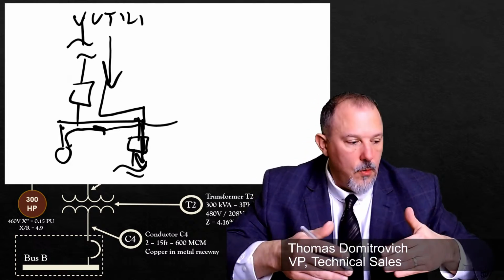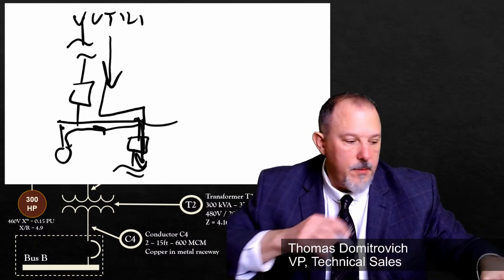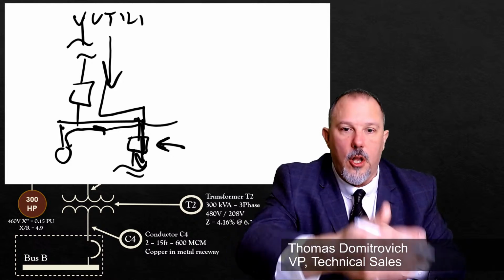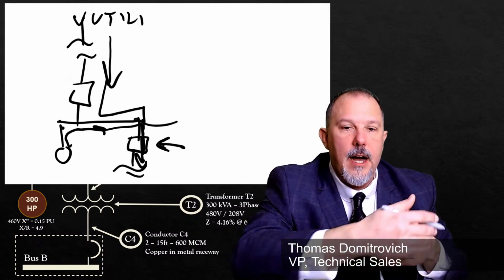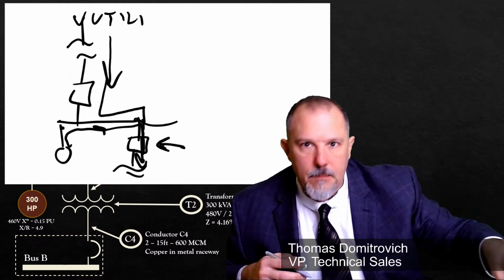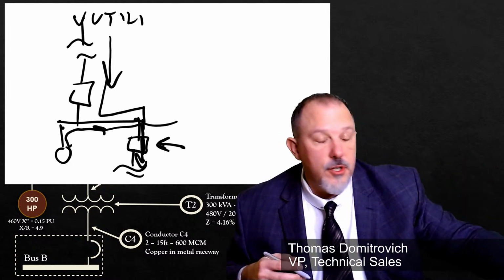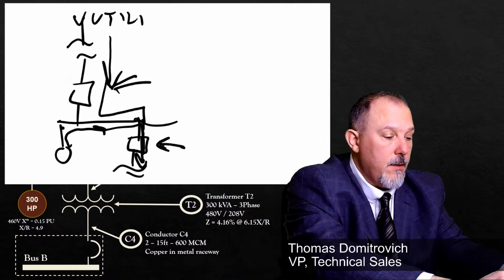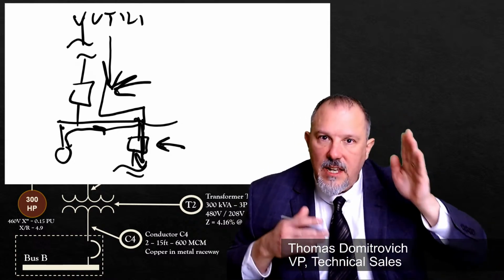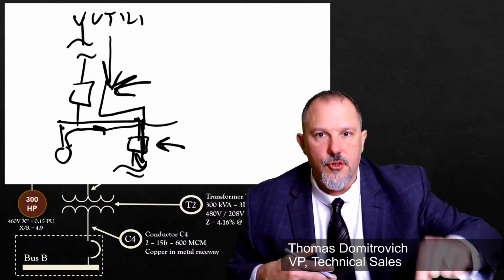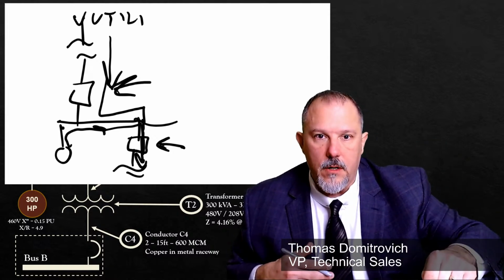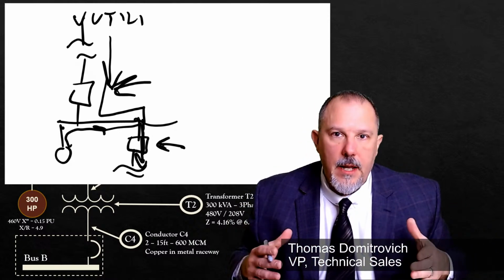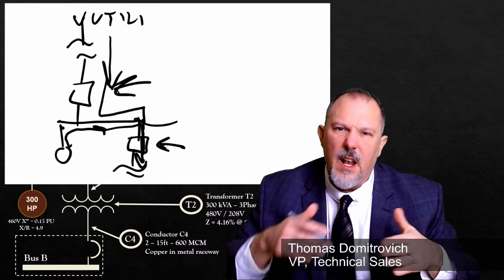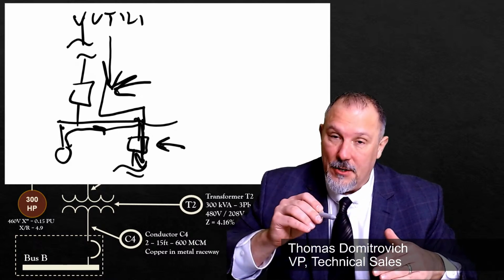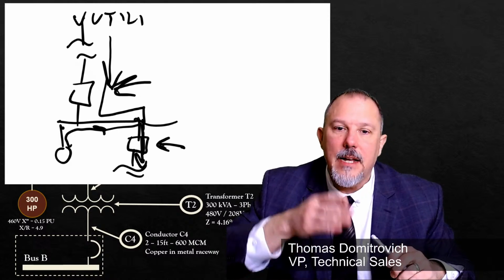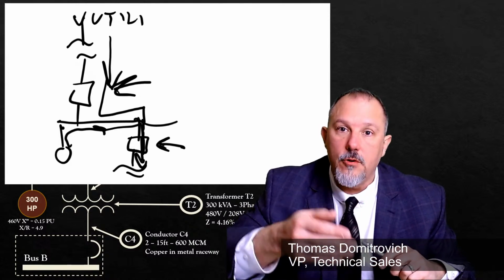So if I want to make sure that this downstream circuit breaker that's closest to this transformer where the fault occurs, I want to make sure that whatever the fault current is, it's flowing through that breaker, which is probably very close to the fault current that's flowing through the upstream breaker. I want to make sure that when they both see that fault current, only the downstream breaker opens and clears the fault. There is no way for me to tell you the likelihood. Remember, you got to think about likelihood of a miscoordination unless I do some evaluation to a fault current value.